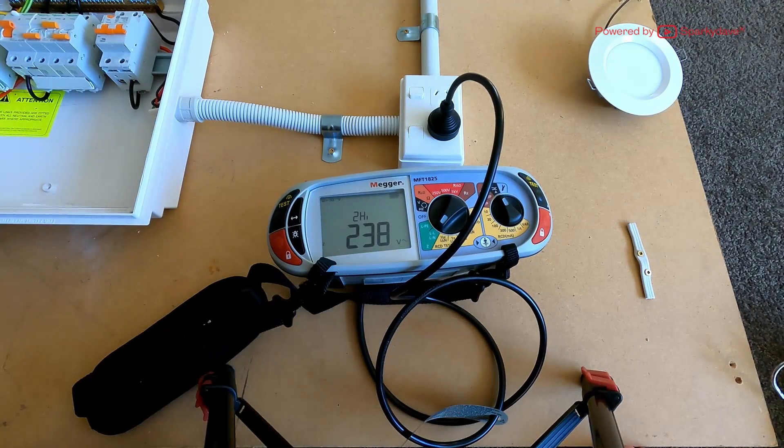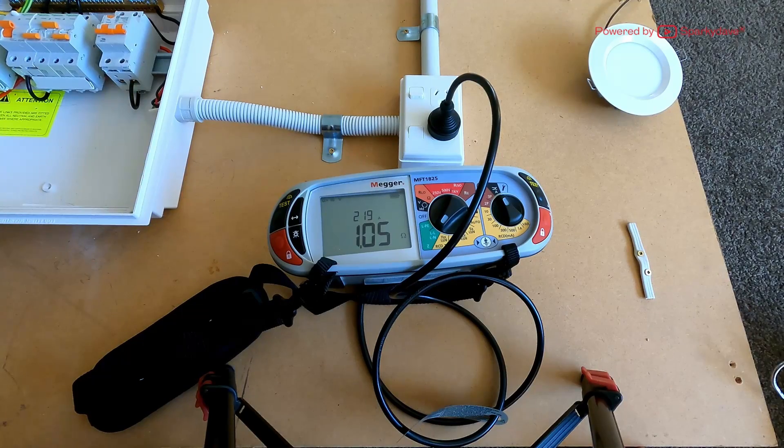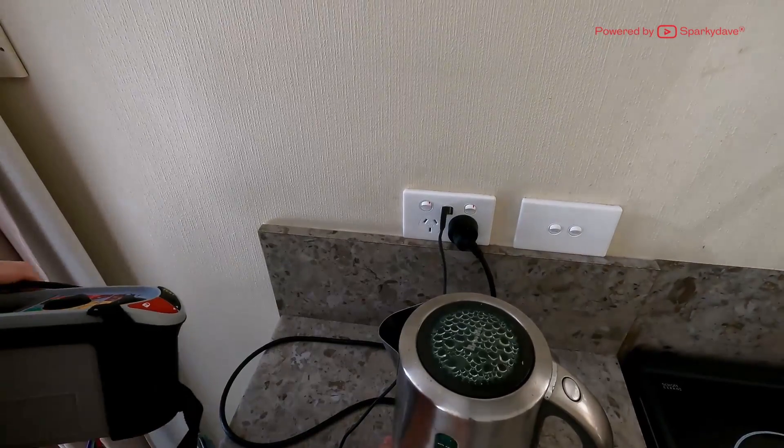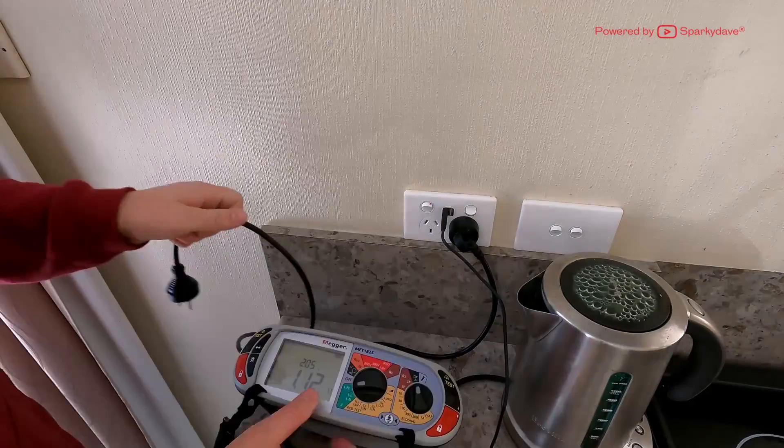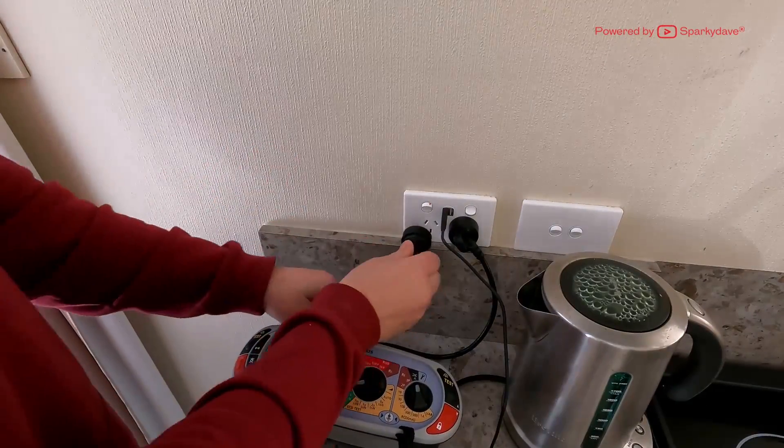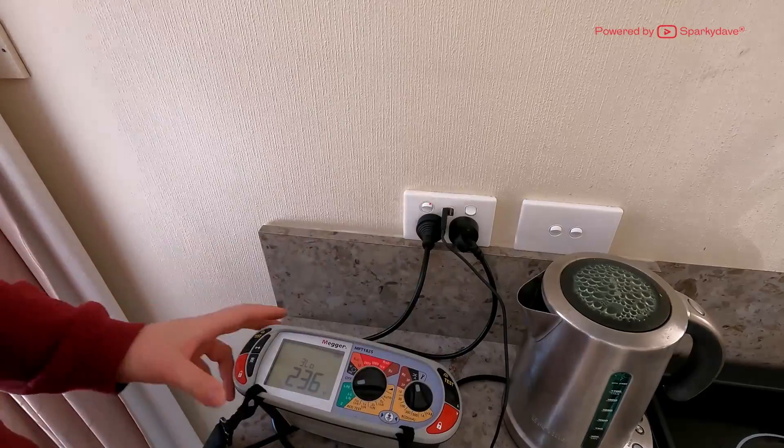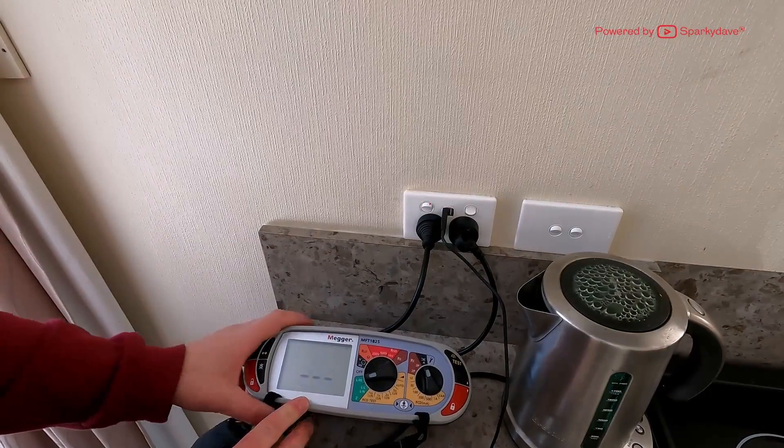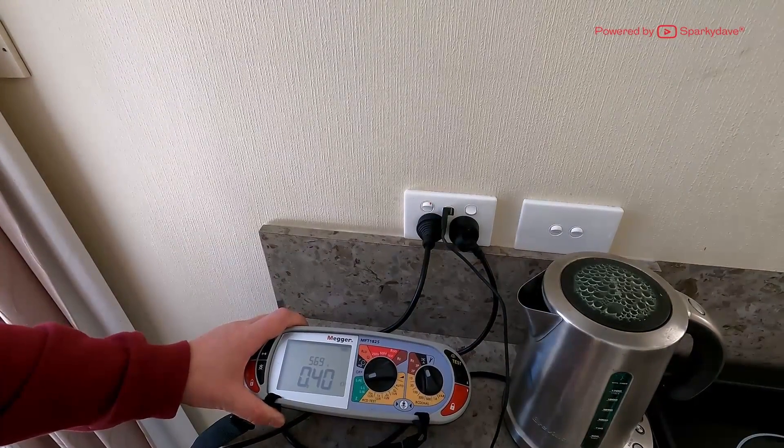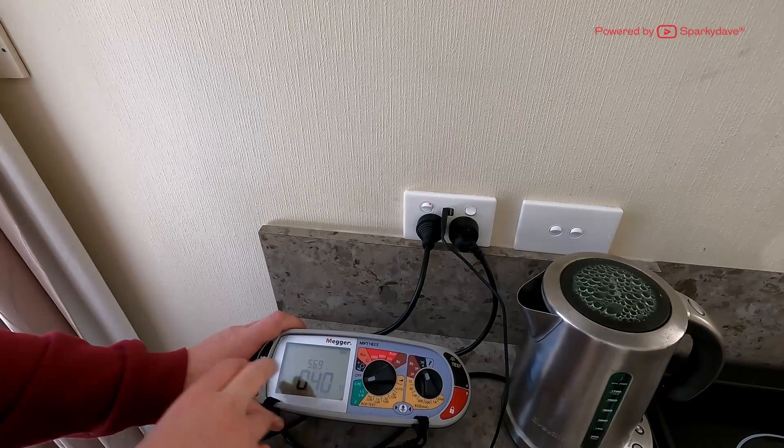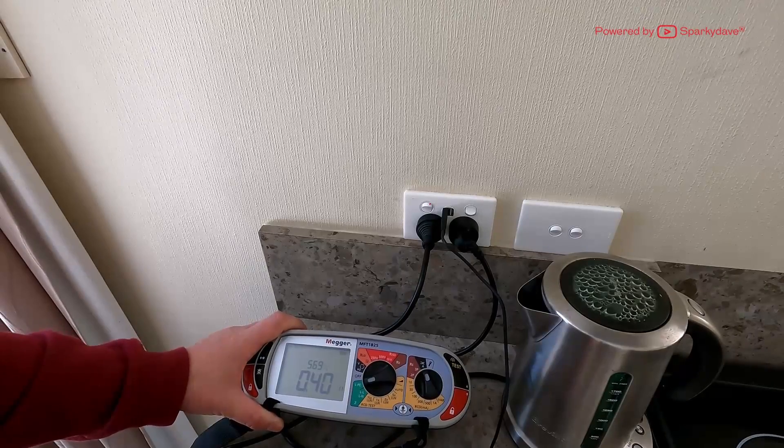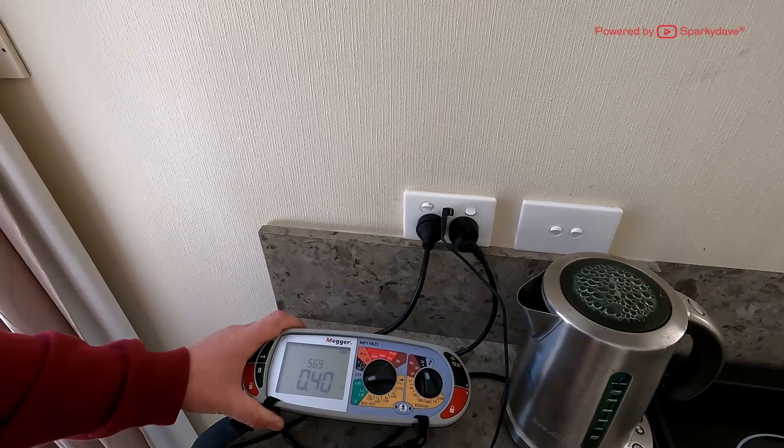So what I've got here is a socket that's much closer to the point of supply, so I'll just do one here to show you what sort of results we do expect. And there we go, that's a much lower impedance. It's much closer to the point of supply, and of course there's a higher prospective fault current that's going to be produced.